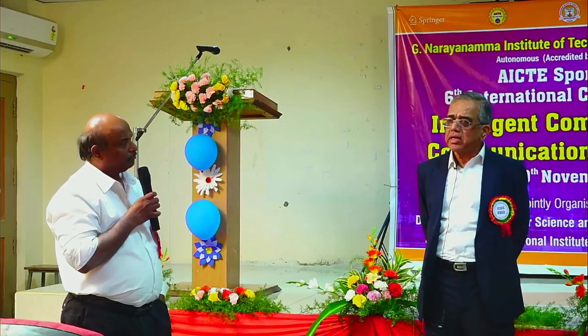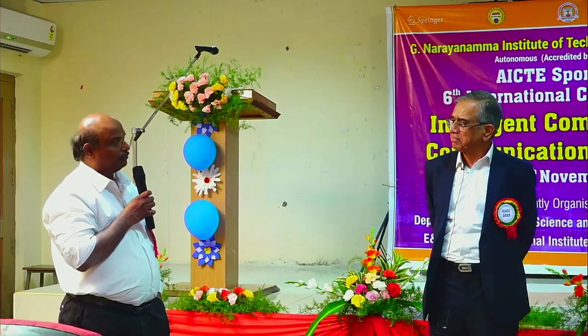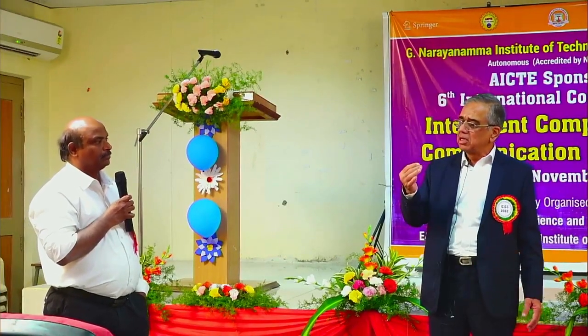It is not necessary. Why? Because when you design a control system, you have to define what the response time needs to be. Any control system has mechanical components, and they have a certain response time - a few seconds. You cannot operate a valve by going from 0 to 100% open in a short time like electronic switches do. It takes time. If a control rod has to move up and down, it has to move at a certain rate. So there are inherent time constraints.